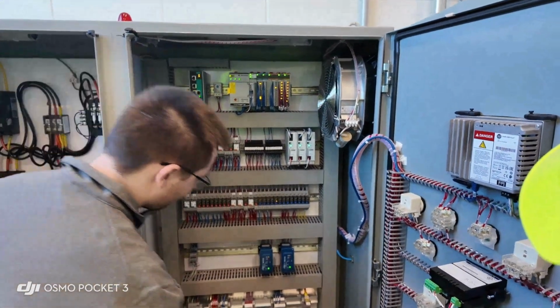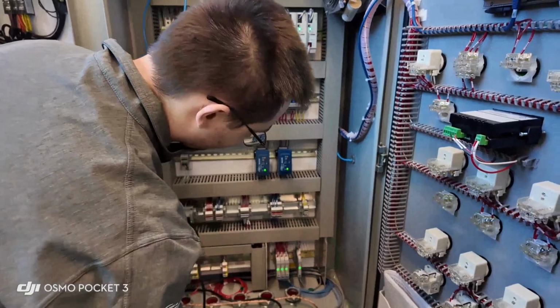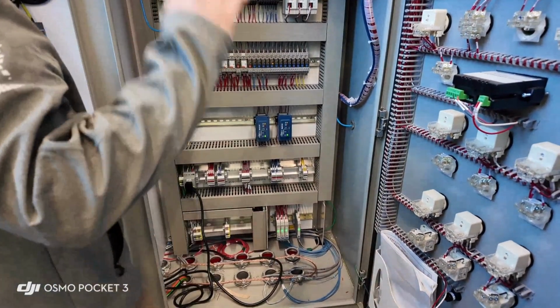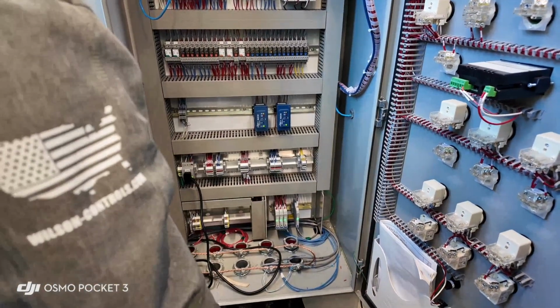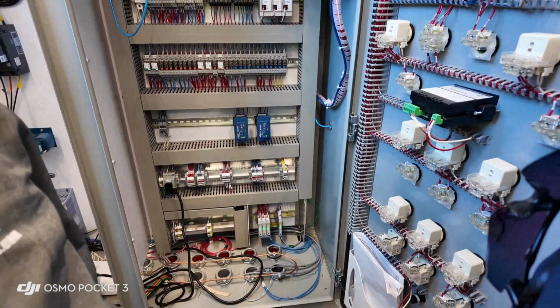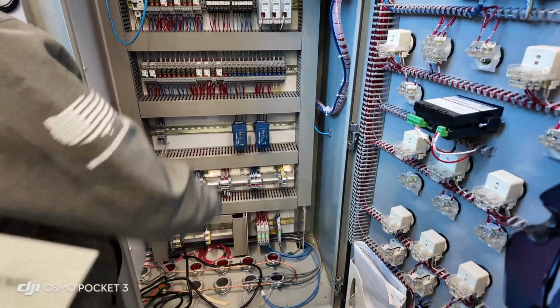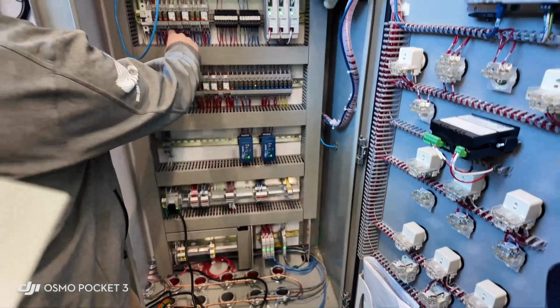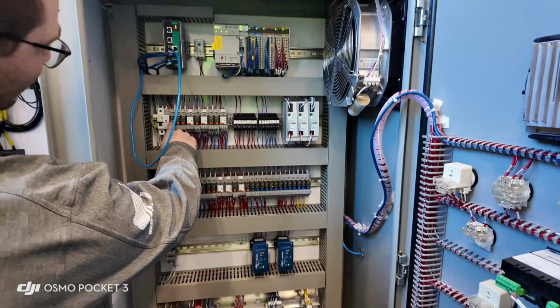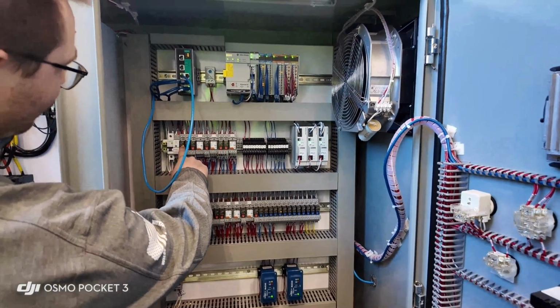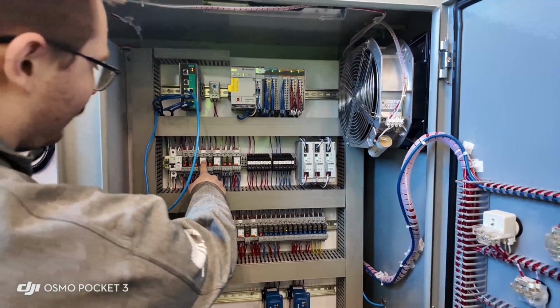LSHH, this is your high level float. It comes in from these ISRs down here, which are used to prevent sending voltage you don't want to a hazardous location down in the wet well. It prevents explosions. And so when the high level comes in, it's going to activate this. You can see the indications. This means that the relay's active. So if it's active, you have a nice indicating reference.